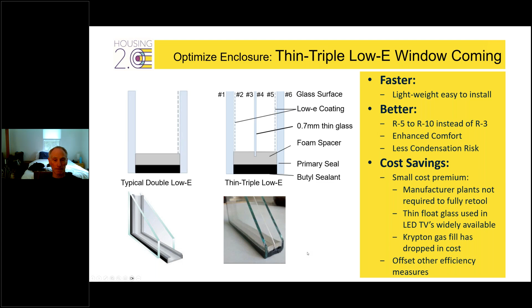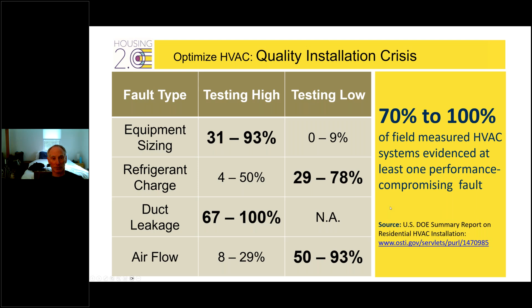Moving on to HVAC is the next thing you have to optimize. I won't go through all these numbers, but 70 to 100% of field-measured HVAC systems evidenced at least one performance-compromising fault, and duct leakage tested high in 2/3 to 100% of a very substantial sample—this is a study done by the National Renewable Energy Laboratory. Sizing was also a big issue, with 30 to 90+% of homes testing way too high.